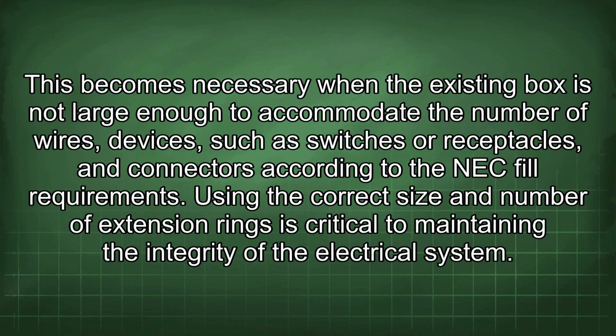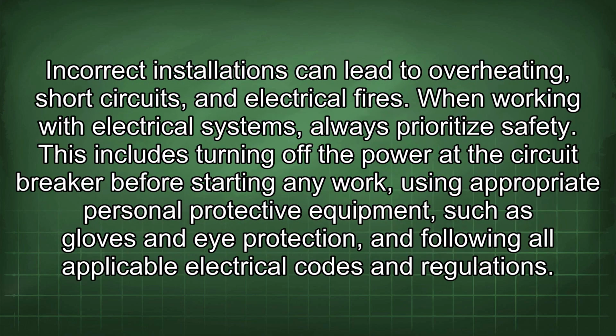This becomes necessary when the existing box is not large enough to accommodate the number of wires, devices, such as switches or receptacles, and connectors according to the NEC fill requirements. Using the correct size and number of extension rings is critical to maintaining the integrity of the electrical system. Incorrect installations can lead to overheating, short circuits, and electrical fires.